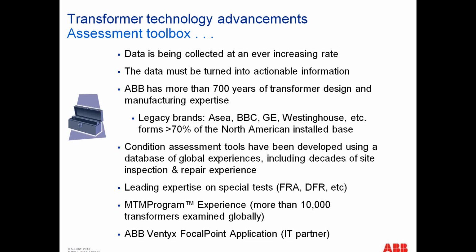Now we've got data collection devices ranging from temperature gauges to sensors on bushings and online gas chromatographs that are constantly sampling the oil on the transformer. The utility or industrial customer that owns the transformer has fewer people than ever to deal with their fleet, so data is being collected at an ever-increasing rate.